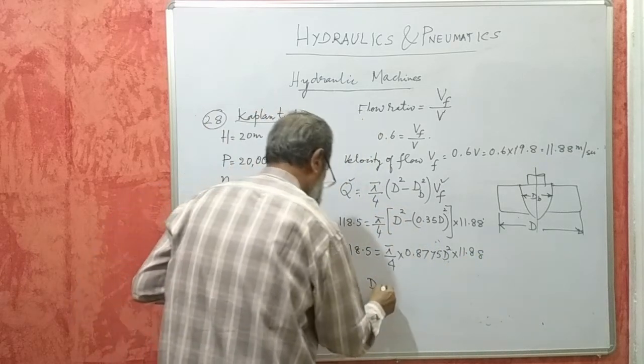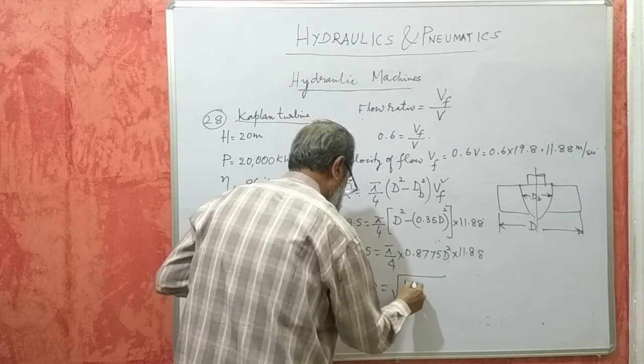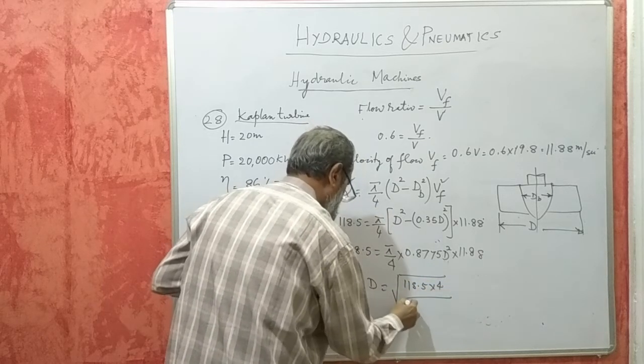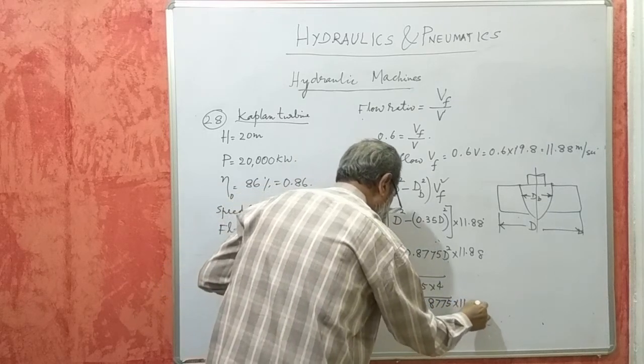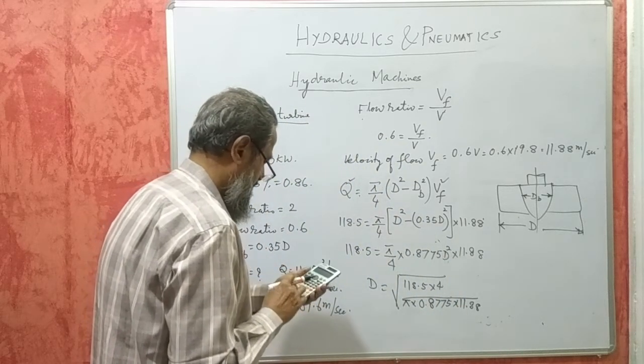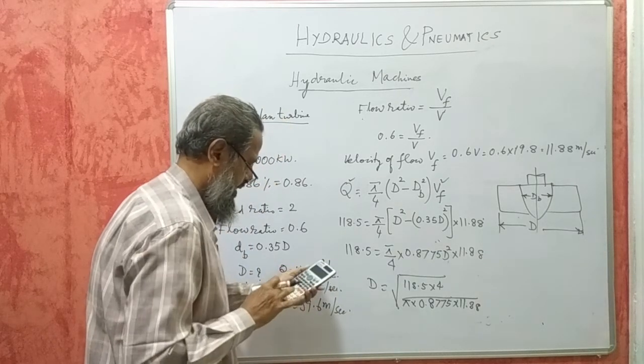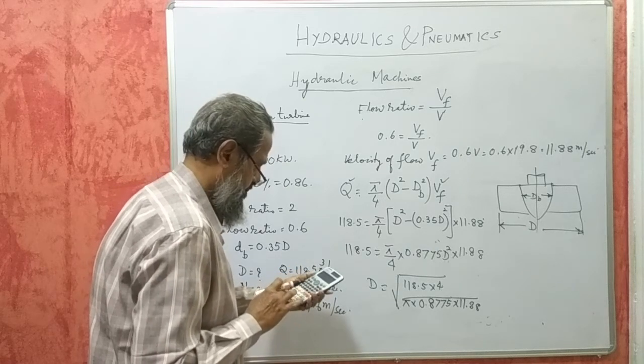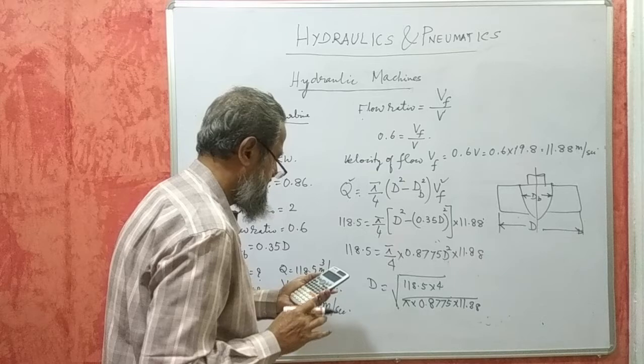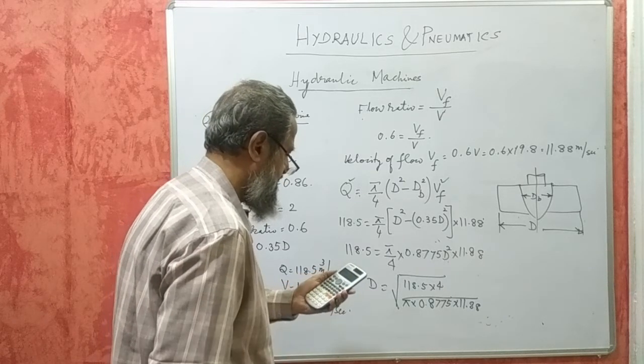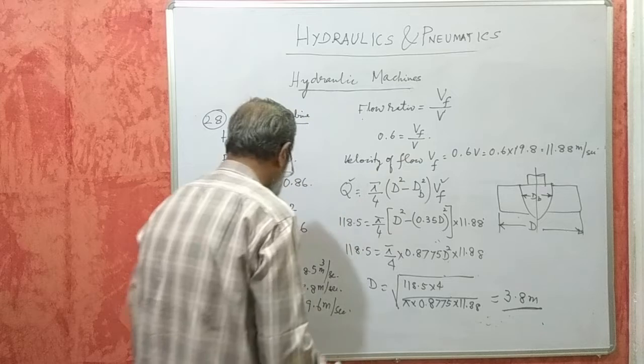So capital D, that is the diameter of the runner we want, d will be equal to under square root 118.5 into 4 divided by pi into 0.8775 into 11.88. That will be 3.8 meters. This is the diameter of the runner.